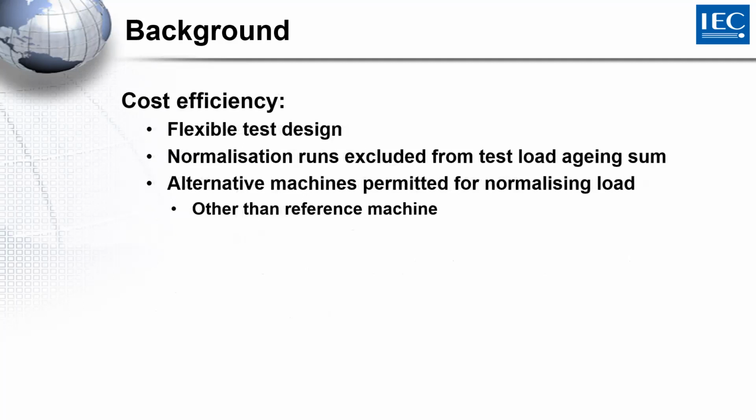Cost efficiency. With a flexible test design, we can produce a test that meets the requirements, but at maximum cost efficiency. The normalization runs are excluded from the test load aging sum, and alternative machines are permitted for normalizing the load, other than the reference machine. Next, please.